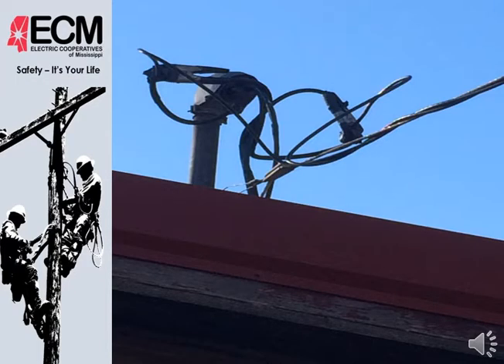The next few pictures I've added to this program. My method behind my madness here is to get you accustomed to looking at what you're walking into. Our inspection on a meter base shouldn't start with the meter base, it should actually end at the meter base. Your inspection should begin at the road, on the main line, on the transformer, on the connections on the service on the transformer, the actual service drop itself, ending at the weatherhead, and then the meter base would be your final stop for the inspection.